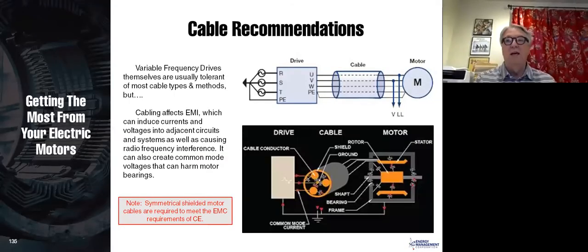Now let's take a look at VFD cable selection. Why would you need a special cable for VFDs? Well, one of the things is VFDs' carrier frequency is 2, 3, 4, 5 kilohertz, and that causes noise that can actually propagate through the air. So if you have walkie-talkies, radios, sometimes you turn on the motor and you get noise. Also, this noise can propagate by capacitance to other wires that might be in the same conduit. That's why we should never, ever run your emergency stop or your thermal measurements or anything in the same conduit with the VFD power wires, because you will get noise induced in those wires.